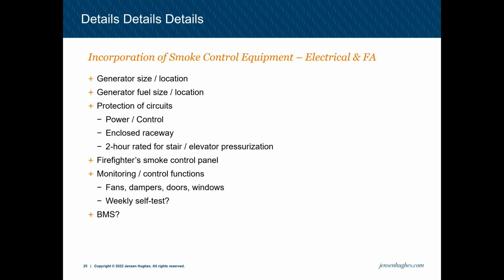So there are ways to omit the weekly self-test. That does require AHJ review and approval, and does usually require some additional monitoring. So tracking that and getting ahead of that in the design phase is very good. Lastly, there's BMS and seeing what kind of interaction your BMS has with smoke control, because if your BMS has involvement with smoke control, it must be UUKL listed, and that adds a premium to your BMS system.